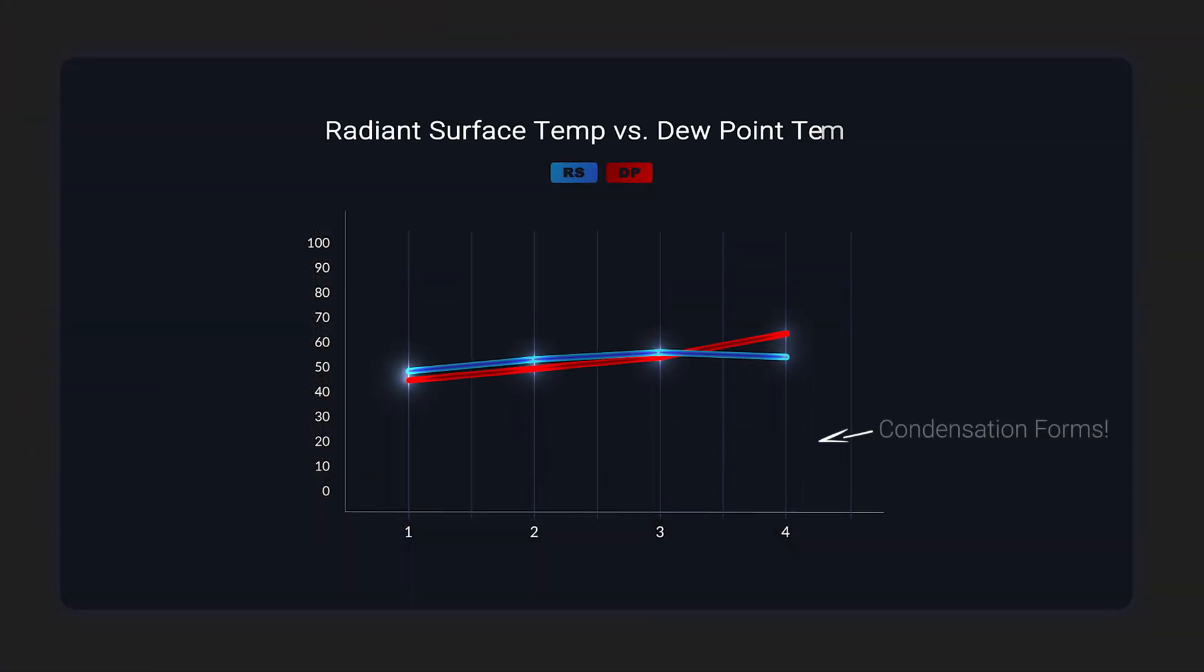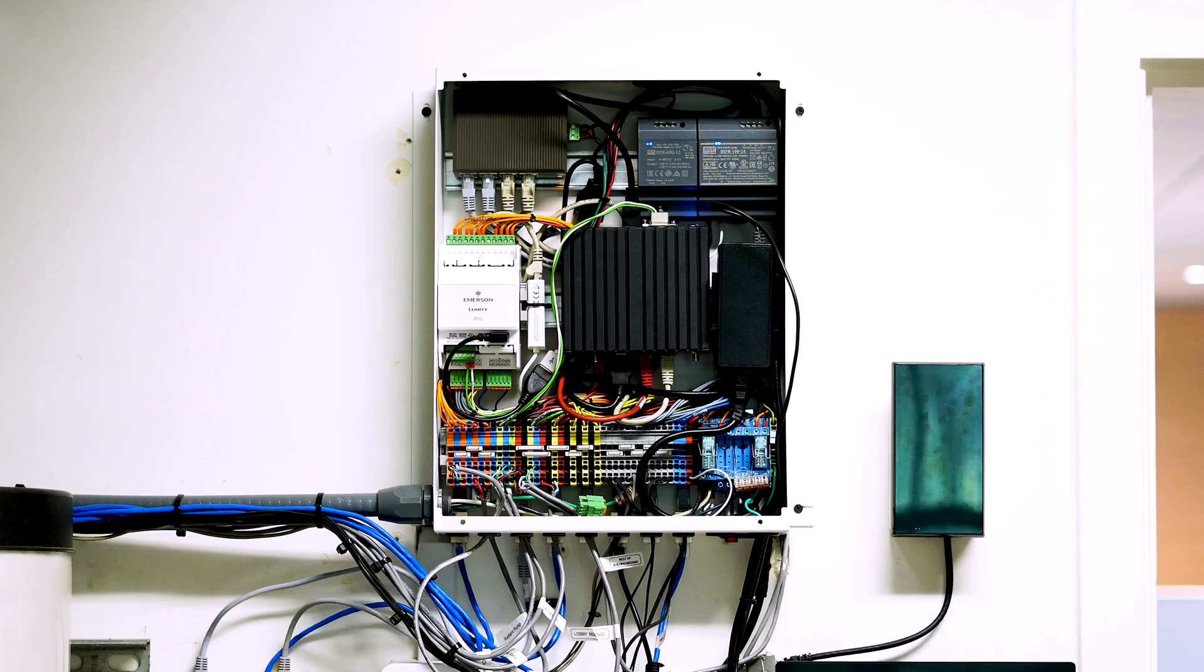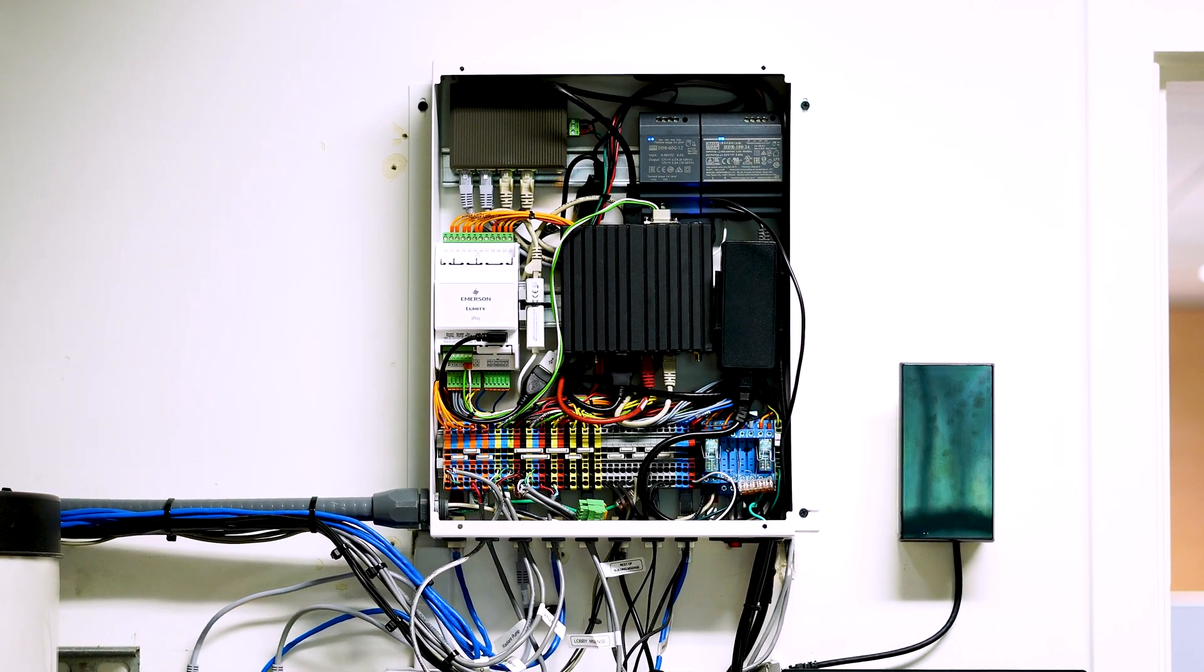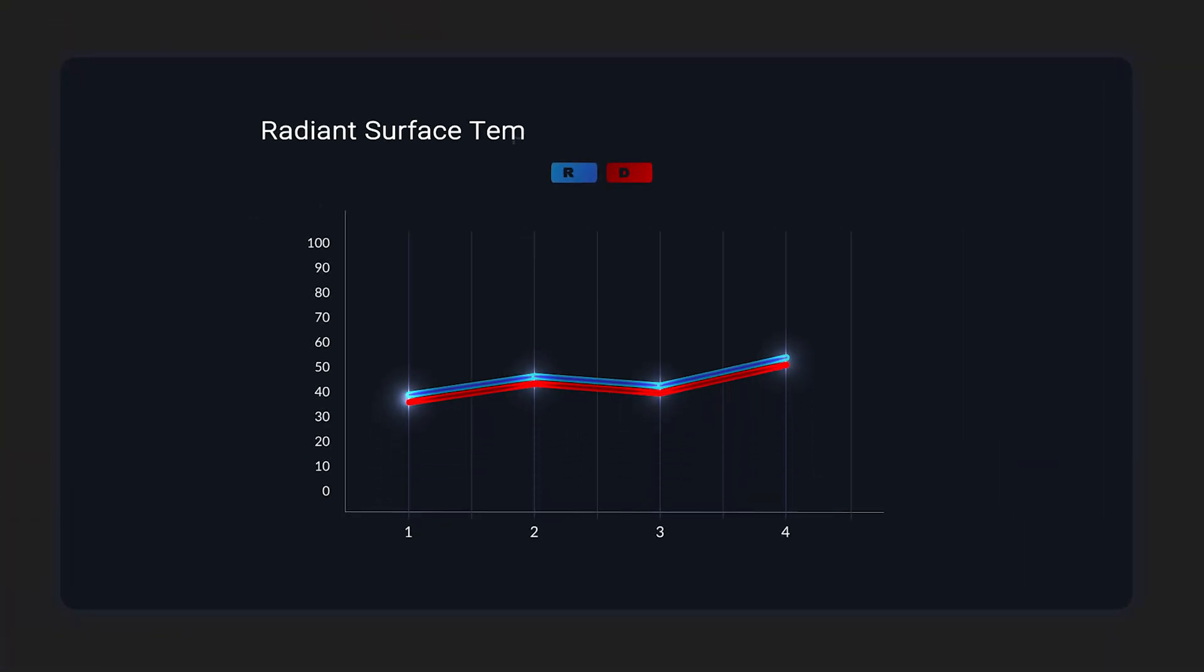The dew point is when condensation would form, and we can't allow that. So we have to use intelligent sensors which monitor that dew point, and then controls which adjust the supply water temperature to the radiant surface to make sure it never falls below the dew point.